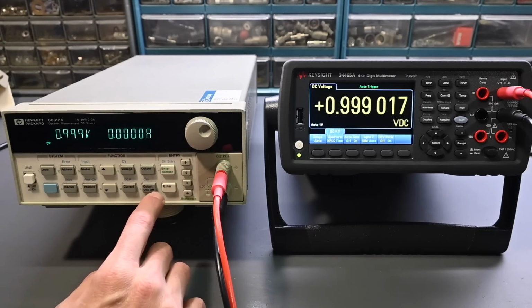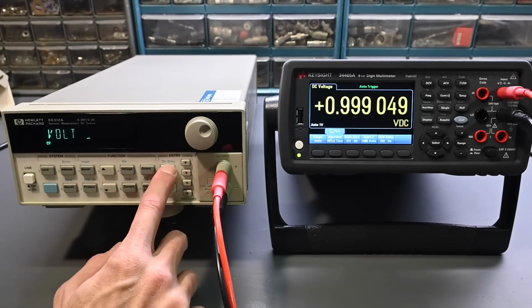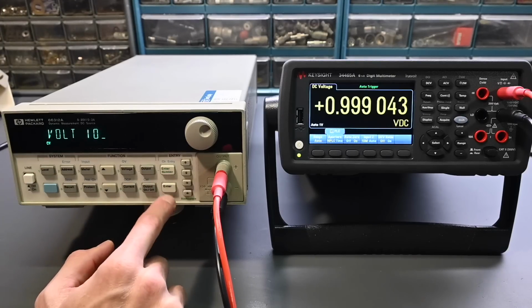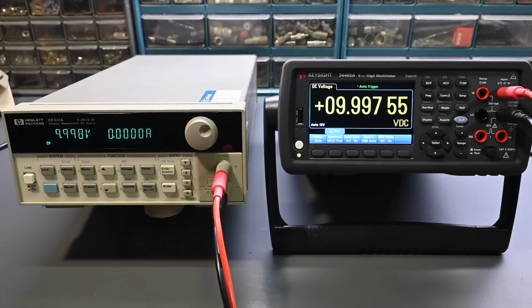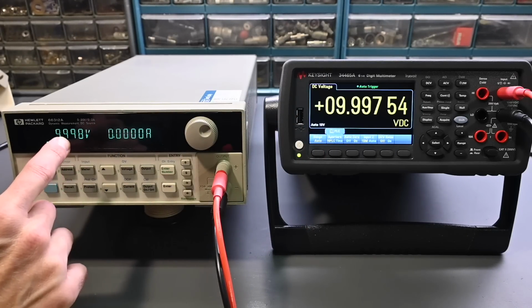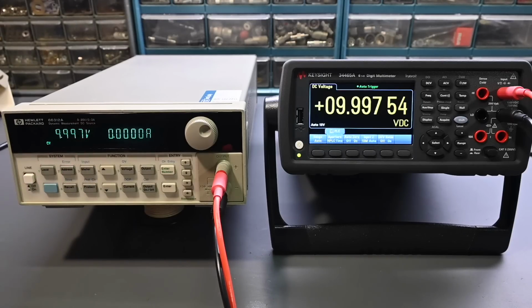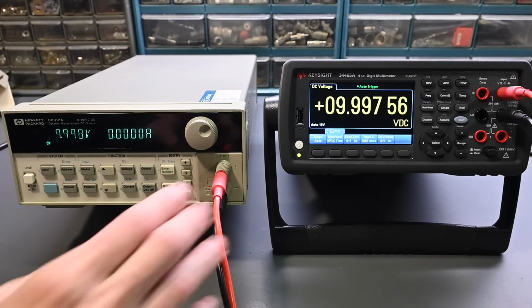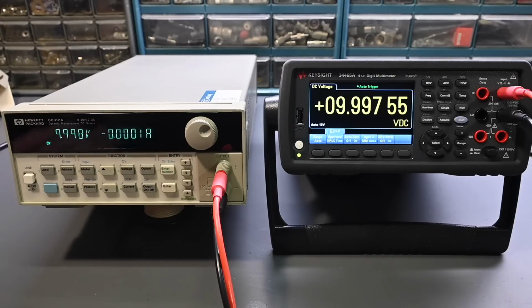Let's go to 10 volts. So go voltage, enter 1, 0, enter. So again, numbers are basically in agreement, sitting right at 10 volts. Very close. I wouldn't be surprised if this slight discrepancy, being off from 10 volts by just a couple millivolts right there, could be because the calibration again was done on the front panel rather than the back panel. So again, I'm going to redo that calibration anyways, but still looks very, very close.